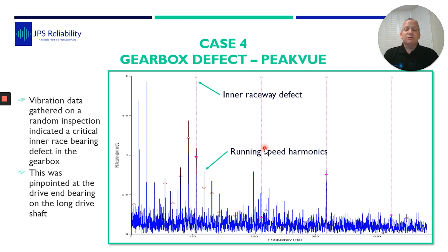This was the PeakVue data from the short shaft. You can see two g's, but what we can see very clearly is an impact which matched the calculated defect frequency for the inner raceway, side-banded by running speed harmonics and harmonics of the defect. The inner race defect energy was so high that it transferred from the rolling element to the outer race to the casing — the outside of the gearbox — which itself was shaking at over 100 millimeters per second. We even picked up the modulation as the inner race defect came close to and away from the bearing.